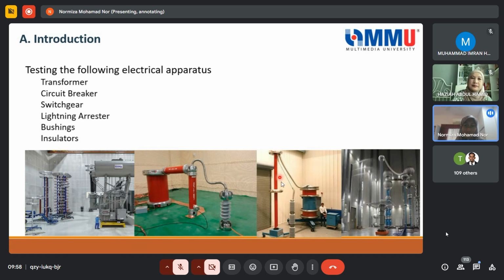But for your case, you can see that this is the capacitive divider. This is the resonant transformer, maybe covered in your generating circuit or generating of high voltage. So this is the resonant transformer. In the testing, this part here is the insulator. The insulator has to be above the ground because it provides clearance. So this one you can also see when we go through the spark gap. For the spark gap, we also have the clearance to provide safety space, not only from the ground but also from the surrounding.